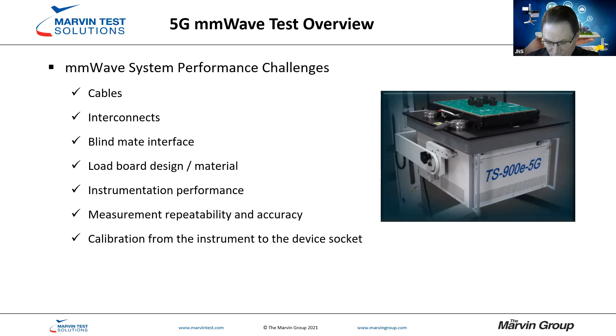find multiple interconnect cables, the associated connectors, blind mate interfaces, and the impact from the load board itself. In the production environment, each of these contributes to the test system error budget, whether it's insertion loss, signal reflections, repeatability, the blind mate interfaces, or the cable performance. And oftentimes, if you measure performance from system to system, simple things when you're dealing with higher frequencies, such as cable routing and having consistent bend radius throughout the various systems, make a big difference because it can impact the overall system performance. So that's where manufacturability comes into this. It's not just an engineering exercise.